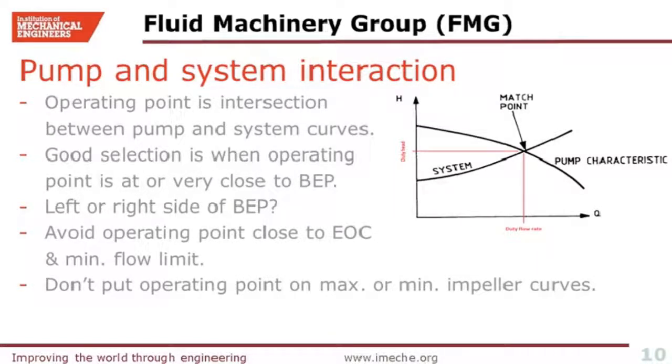So all centrifugal pumps are subject to internal recirculation in both suction and discharge of the impeller when they are operating away from BEP. It is surprising to know that underperforming of pumps is a widespread issue in industry. I was reading an article a couple months ago, in which, several years ago, I believe, a technical research center in Finland evaluated around 1,700 pumps, which were installed across 20 different process plants.